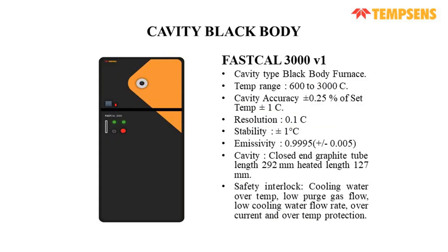Next cavity type black body, we have the FastCal 3000. The temperature range for this model is 600 to 3000 degrees, with an accuracy of plus minus 0.25 of the set temperature plus minus 1 degree centigrade. The resolution is 0.1 degree centigrade, and the stability is plus minus 1 degree centigrade. The emissivity is 0.9995, and the cavity we use in this is a closed graphite tube. The length of that cavity is 292 and the heated length is 127.